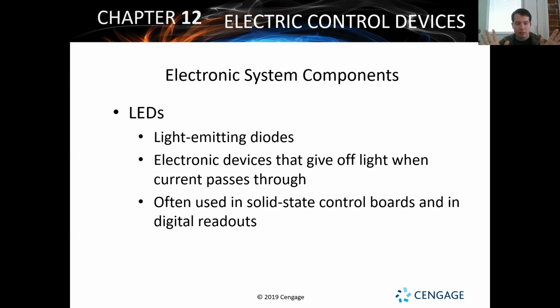Typically, and again it depends on the manufacturer, I'm not going to say it's this way every single time, but typically if you have an LED code, you'll see it either on a furnace or an indoor air handler unit. On the outside panels, when you take the panels off to get inside the unit, those service panels usually have a sight glass - a little cutout section with a piece of plastic over it - lined up right over where the LED is on that board.